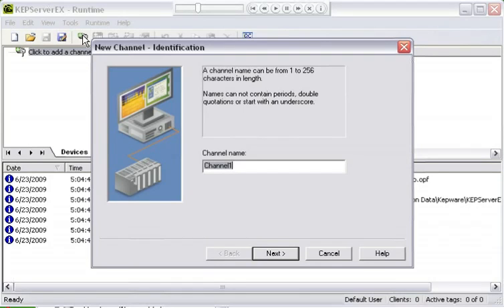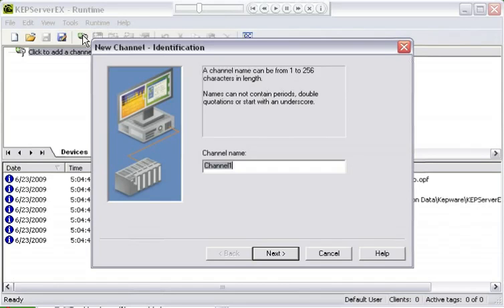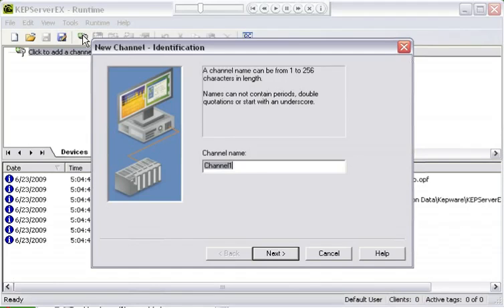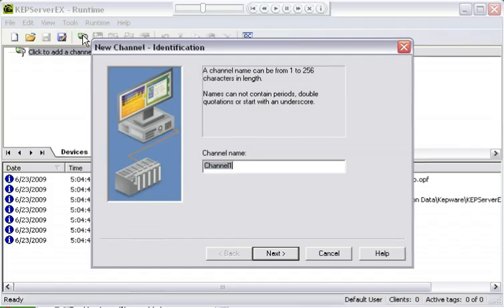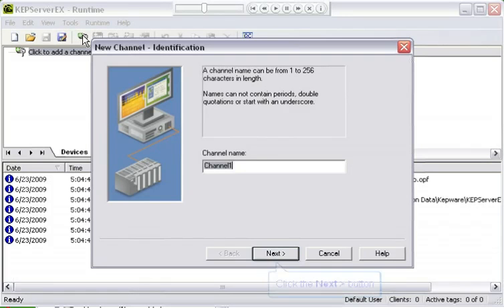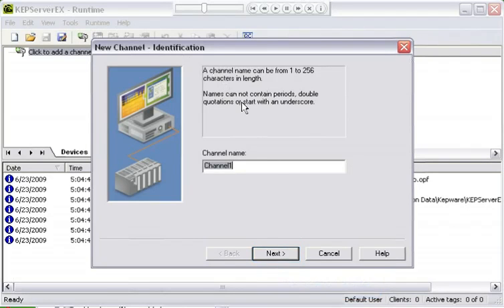You're going to want to name this channel something that reminds you every time you look at it of what it's doing. If this is an Ethernet connection to a certain device, you might somehow indicate that. I'm going to leave the default at Channel 1. Channel Names can be up to 256 characters long. You're going to want to be aware of that, though, because you may have to type this name a lot in a client, or you may have a limit of the length of an OPC item or a DDE item in a client. You don't want to have a channel name and a device name that are so long that you can't fit everything into the address space in a client application. I'm going to click Next to accept the default name.